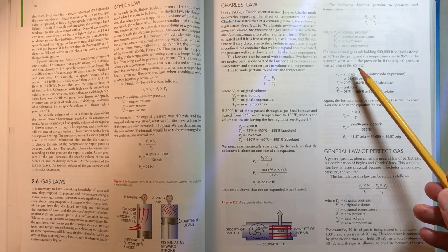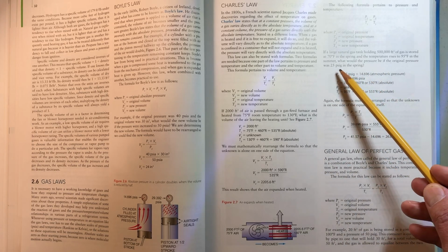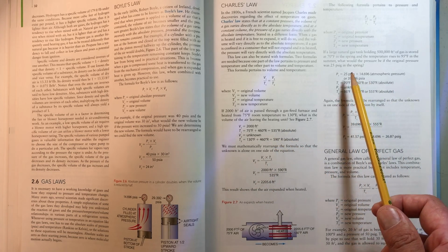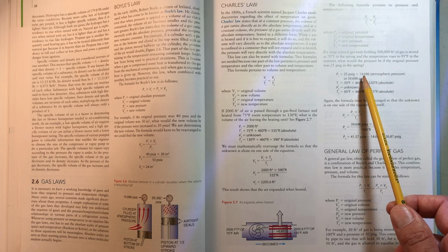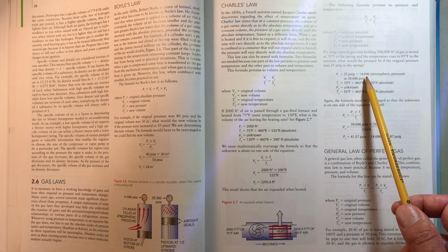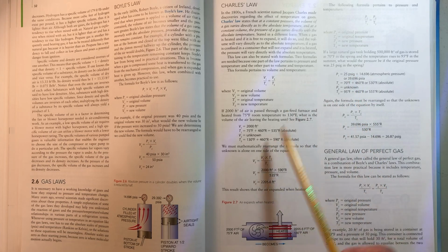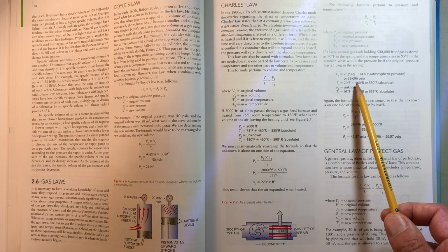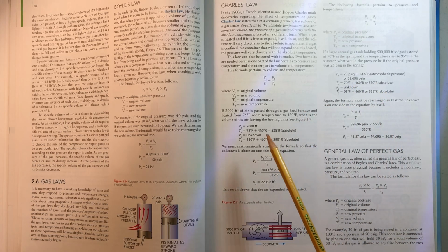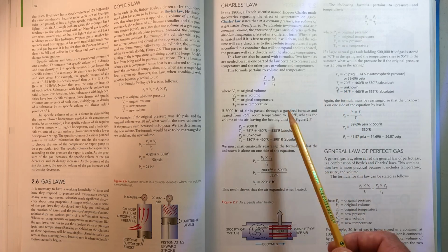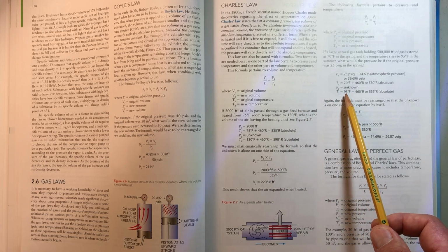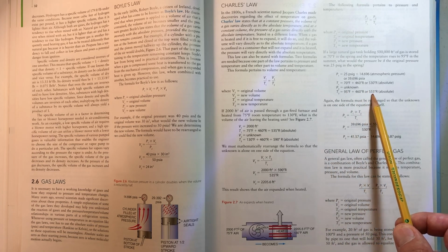So what would the new pressure be if the original pressure was 25 pounds per square inch gauge in the spring? We've got to convert both our temperatures and pressures to absolute, which means we're going to add the atmospheric pressure of 14.69 psi to our 25 psi gauge reading for the original reading. And we're going to add our 70 degrees to 460 degrees to get 530 degrees absolute temperature. We're looking for our new pressure, but we know our outdoor temperature in the summertime is 95 degrees Fahrenheit. We're going to add 460 degrees to that, and that's going to give us 555 degrees absolute.